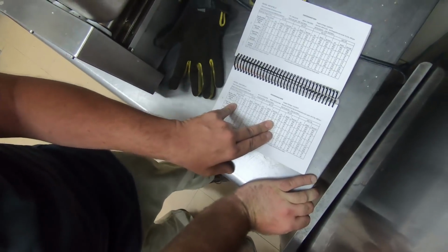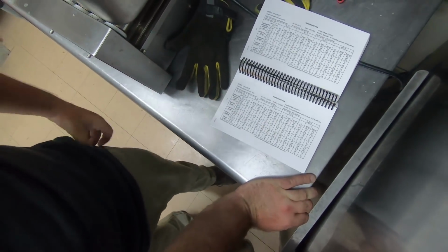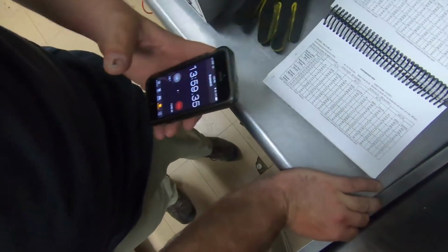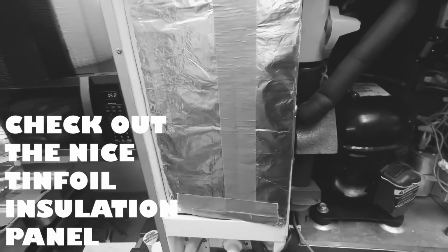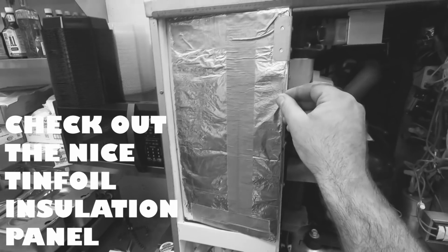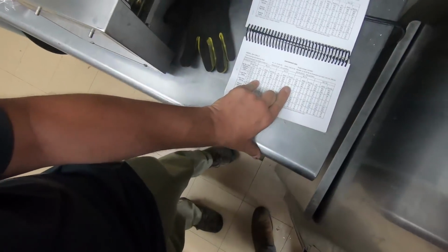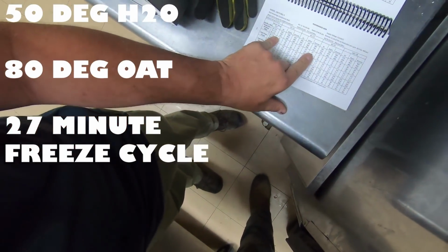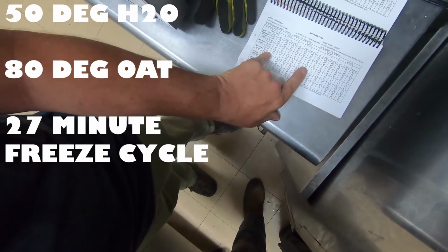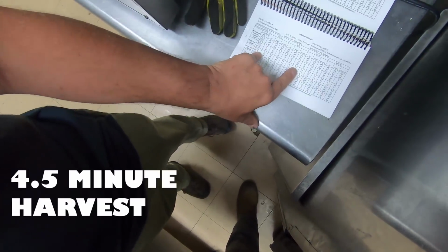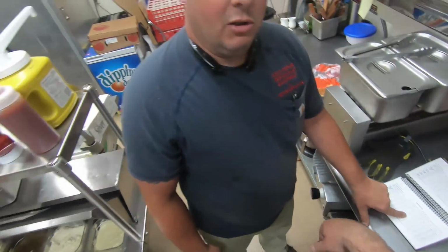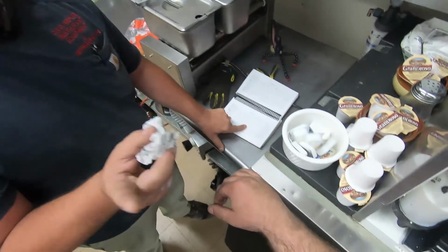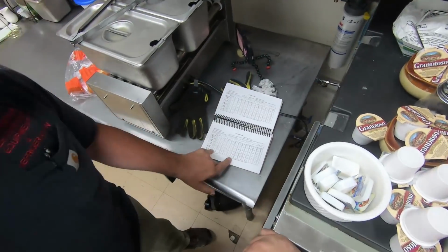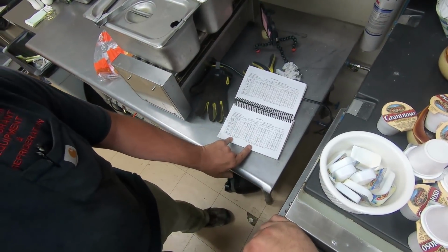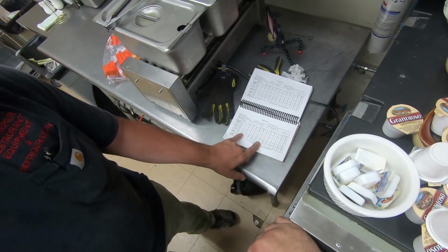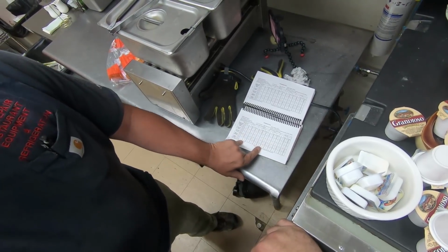Okay. Where are we at right now? Right now, we are about 10 minutes into freeze. All right. And then the same thing here, so you have roughly, with 50-degree water and 80-degree ambient, a 27-minute freeze, about a 4.5-minute harvest. This harvest will probably run a little longer because we changed those dip switches to give it an extended harvest. Okay. And then it also will tell you that 5 minutes into your freeze cycle, it tells you what your pressure should be.